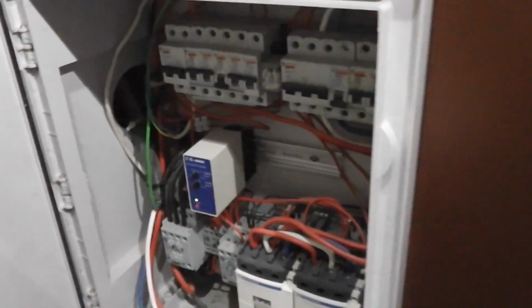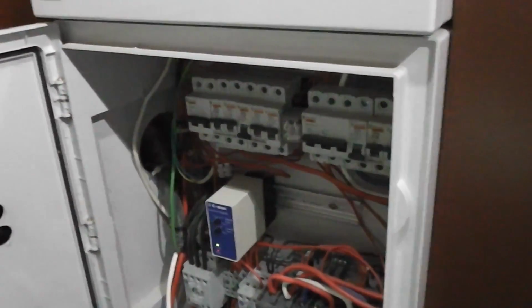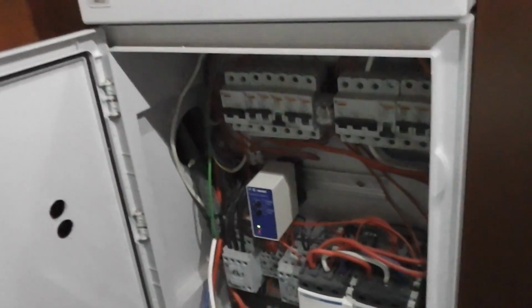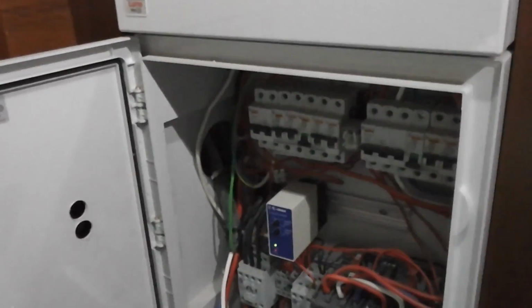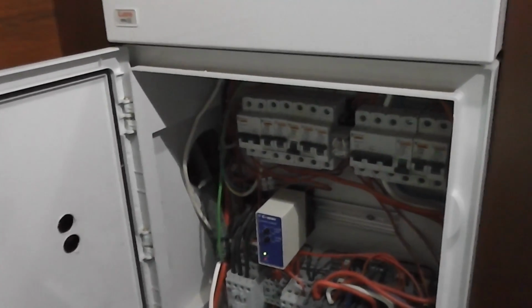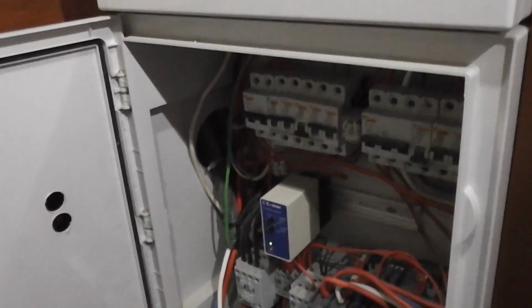As I was saying yesterday, if there's low voltage, high voltage, or no voltage at all, that regulator will start the generator. I won't get into the specifics of how it starts it, except to say I also installed the controller and the automation on the generator. It was just a standard key-start generator, so I wired up a controller and wrote all the software to make it work the way I want.